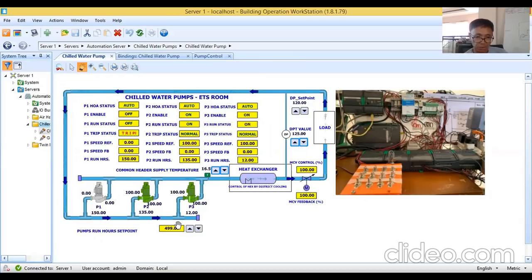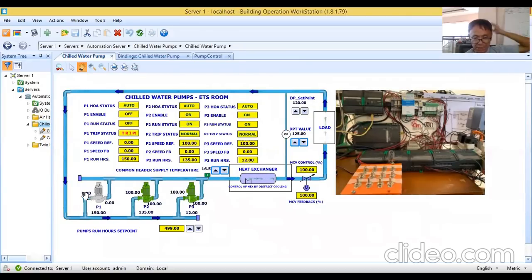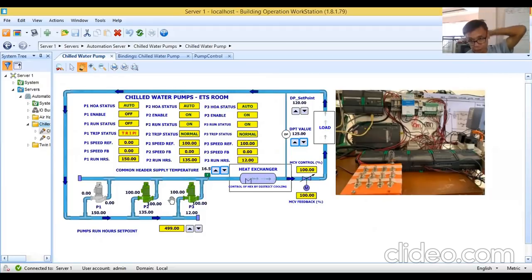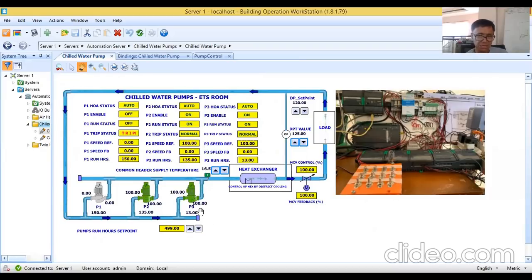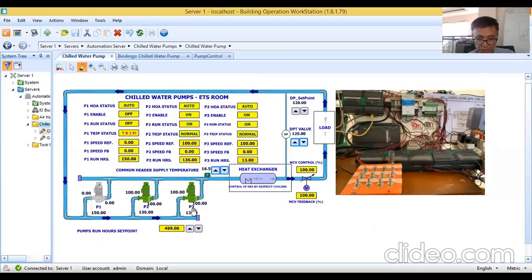Testing pump one trip — trip is displayed, animation stops, control signal is zero, speed feedback is zero. Pump three kicks in with control signal 100, speed reference 100, speed feedback 100. This is simulating the control logic program based on our simple sequence of operation. Removing pump one trip — pump one runs again.